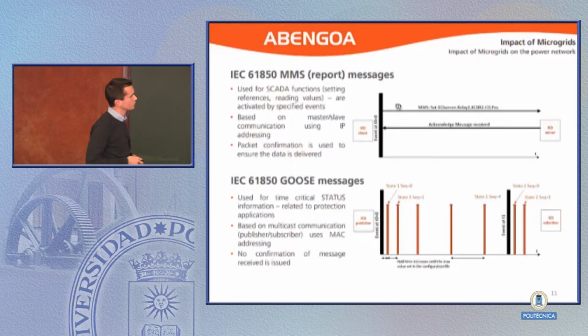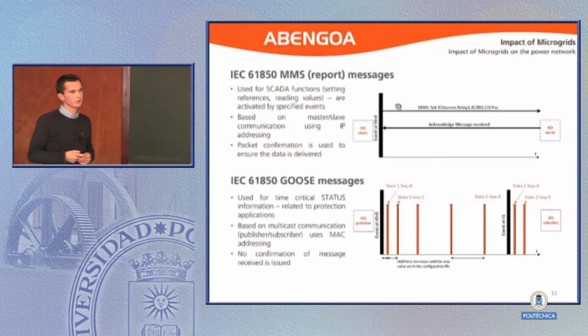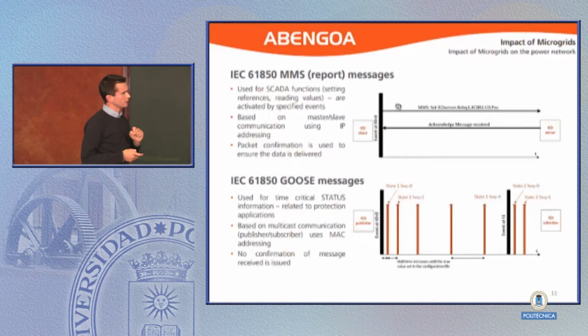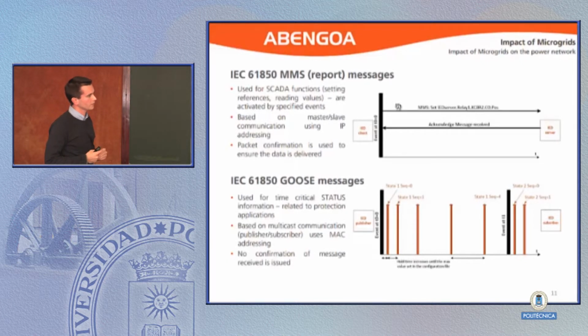The second would be the GOOSE message, which is used to send critical time information between IEDs. To achieve this very small amount of time in transmission, it uses a multicast communication between a publisher and a subscriber, and uses the MAC addressing without any packet confirmation of the received message. And the third one, because I said there is a third one, is the SV, also called the sampled values, which uses the same procedure with the publisher and subscriber, like the GOOSE, and is used to stream data containing measurements from current and voltage transducers. This is used instead of hard wires.